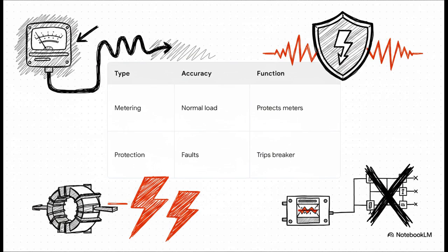Now, these different physical builds really come down to two main jobs: metering and protection. Metering CTs are built for high accuracy at normal, everyday loads, but if there's a huge surge, they're designed to saturate, basically hit a wall and stop increasing output, to protect the delicate, expensive meters attached to them. Protection CTs, on the flip side, are the heavy-duty bodyguards. They stay highly accurate even during massive electrical faults or short circuits. Their job is to tell the protection relay exactly how massive a fault is, so it can immediately trip the breaker and save the whole system.